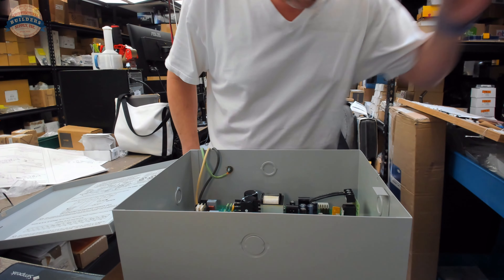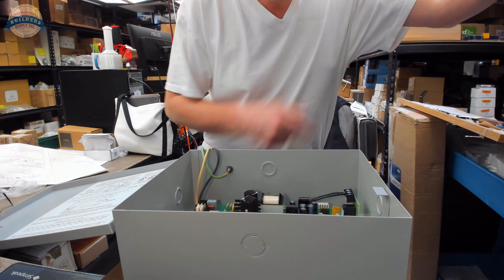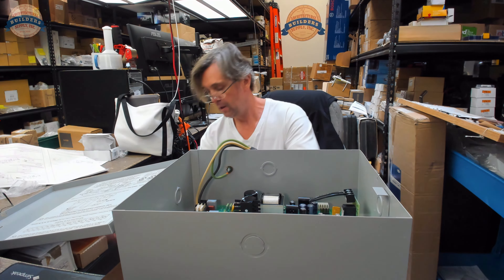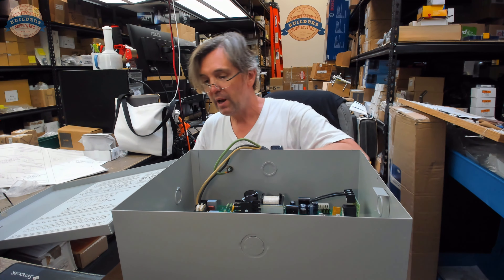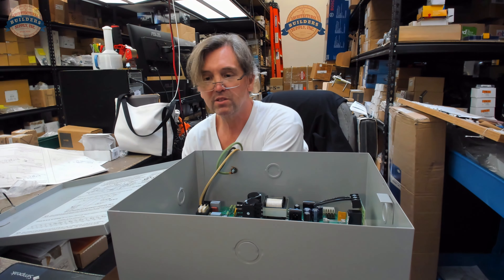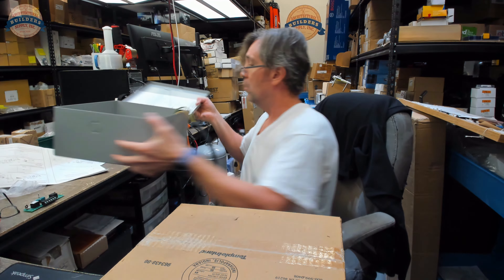Because there was no fire alarm board installed, and the E3 was cut — that's the bottom line. I know the client does not have the fire alarm board, so I'm going to send them the fire alarm board and a video showing how to jump it. Let's switch to the screen view one more time to take a closer look at those installation instructions.